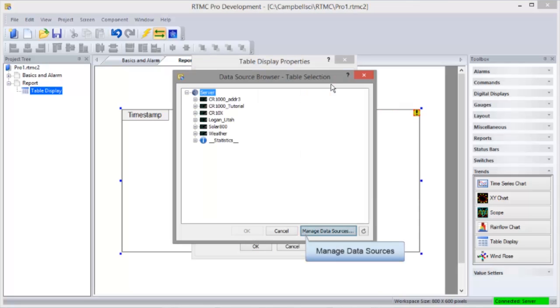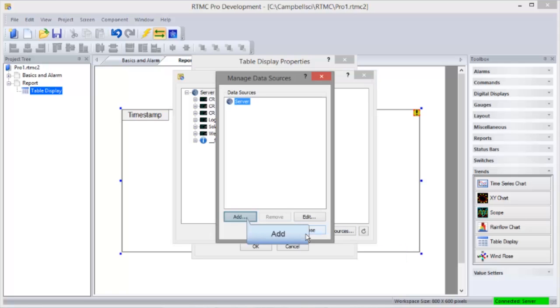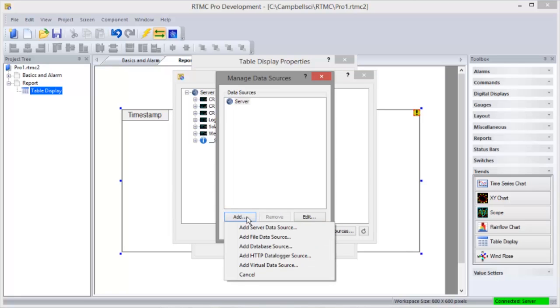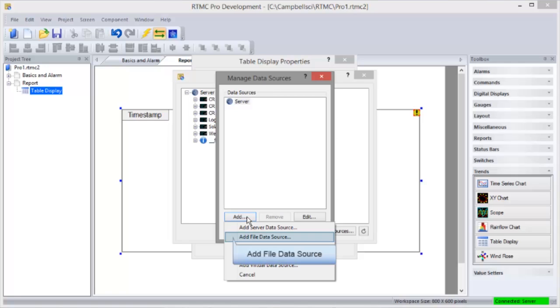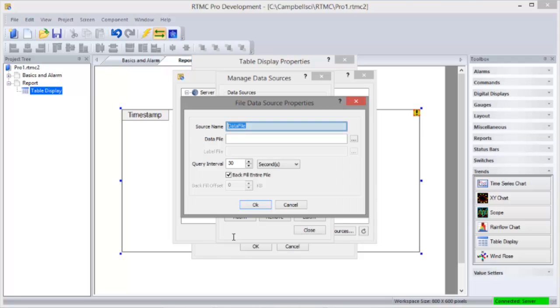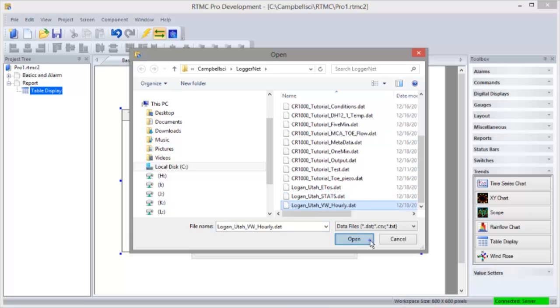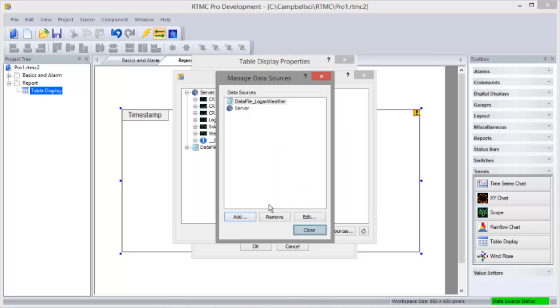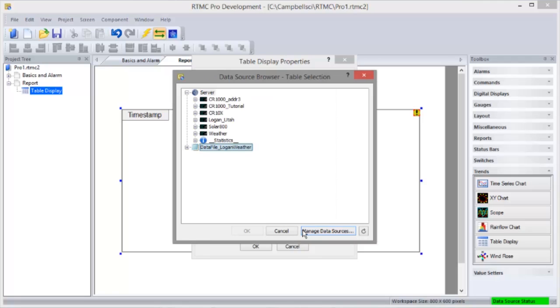This time let's use a data file as our data source. Previously we've used data in the cache from Schedule Collection. A data file lets you view data that has been collected but may no longer be in the cache. Click Add. Your choices here are Server, File, Database, HTTP Data Logger, and Virtual Data Sources. We'll select Add File Data Source. Give the source a meaningful name. I called it Data File Logan Weather. Then browse to the file. That does it. Now your RTMC Pro project can access that data file for display. Here you see it in the data source browser. And we can select the data file.